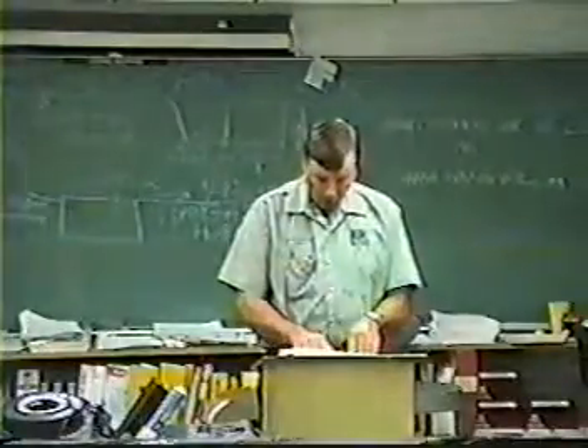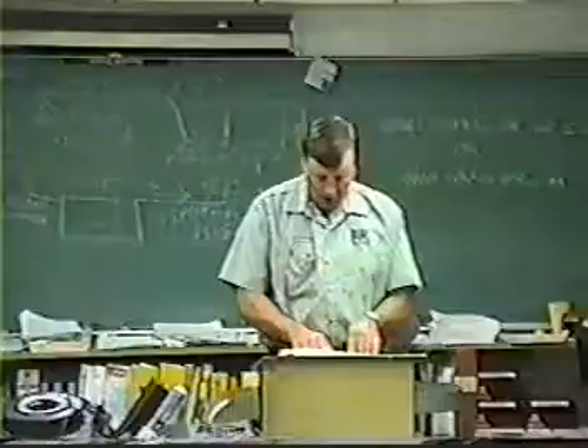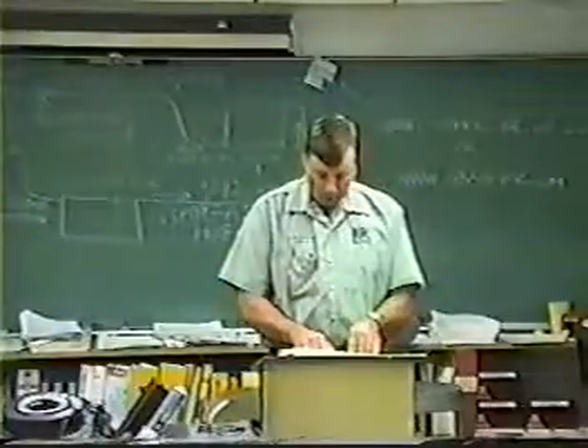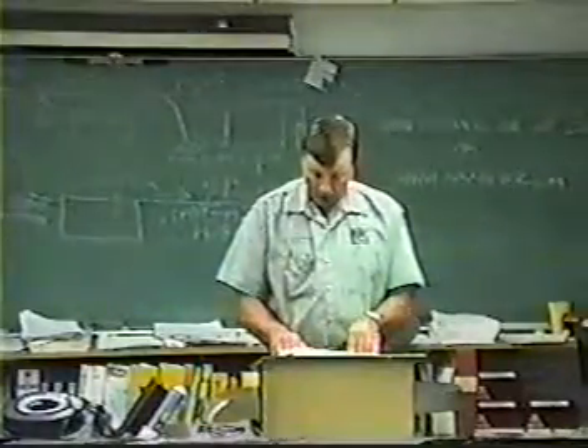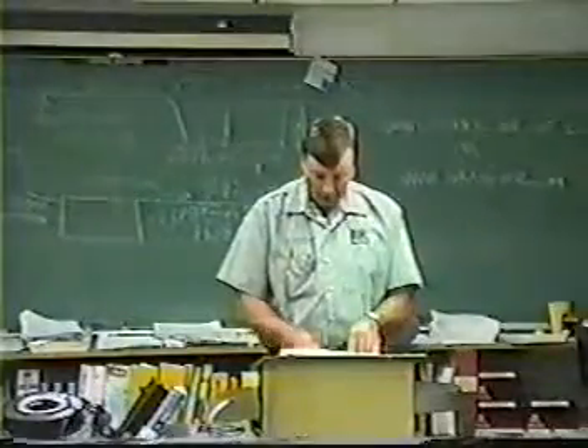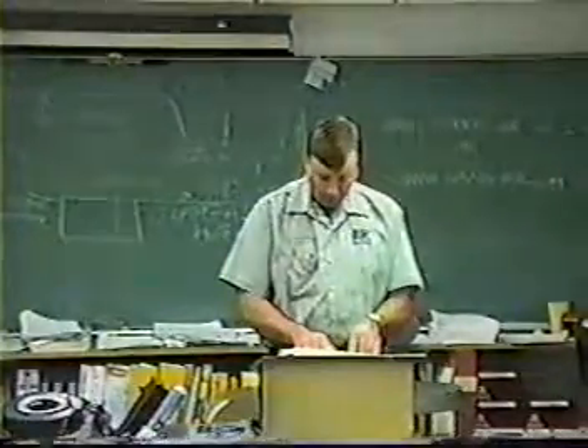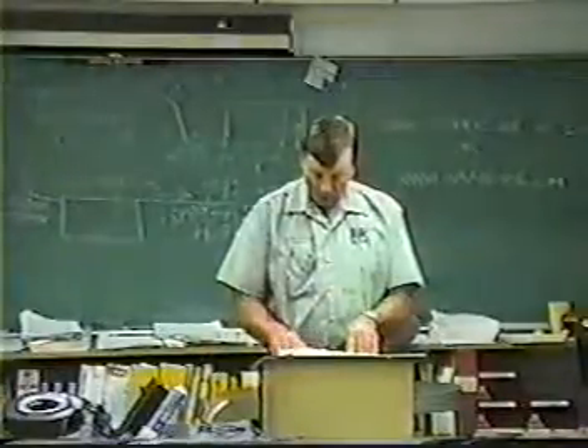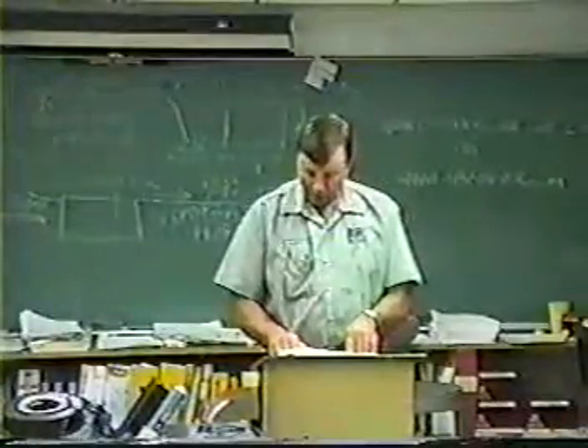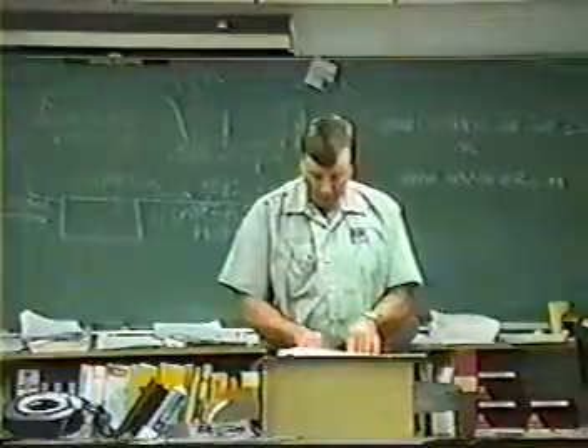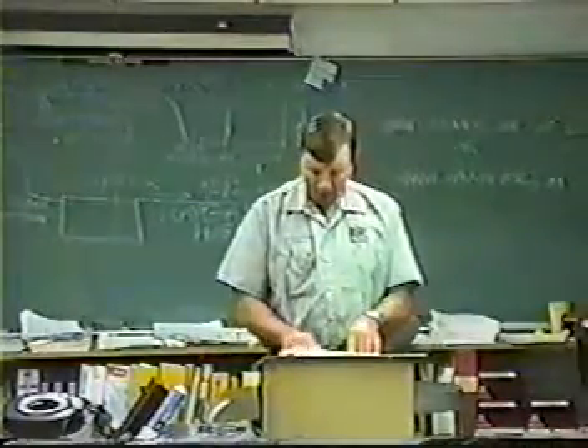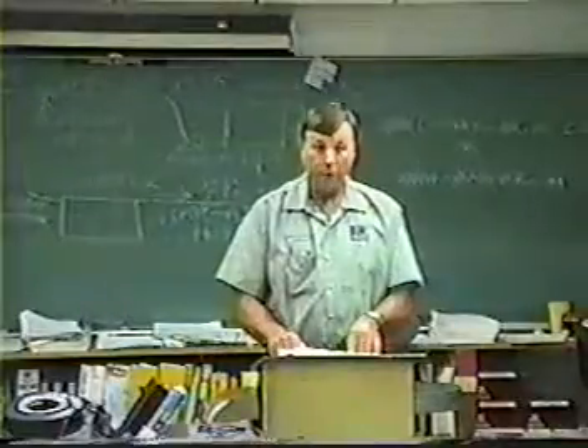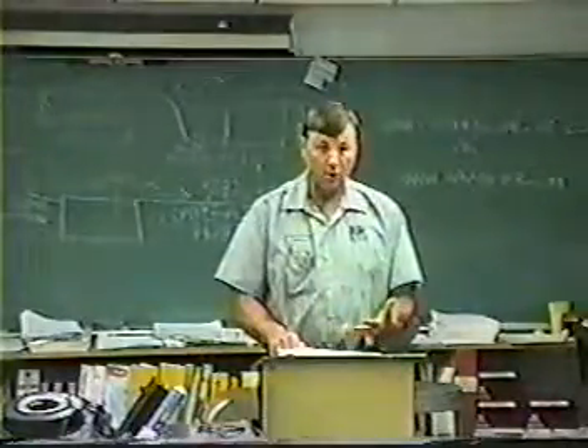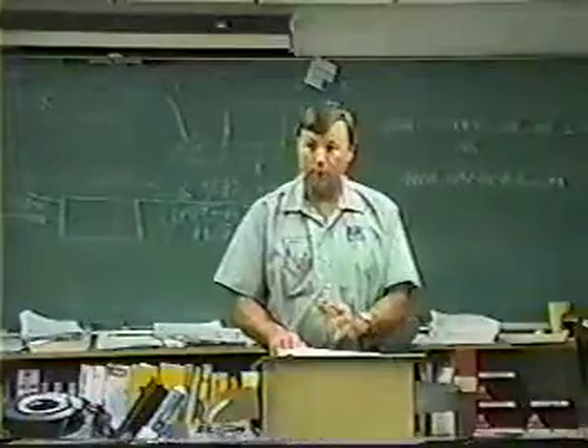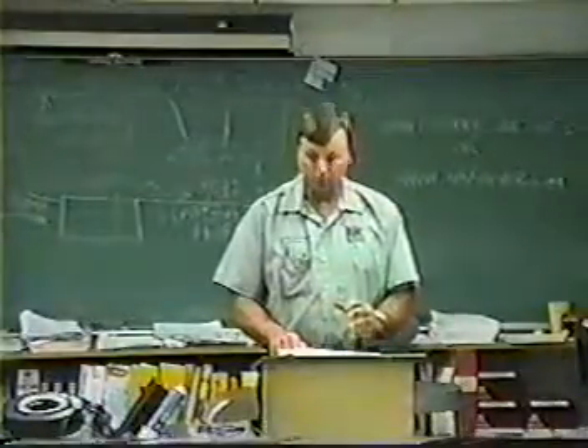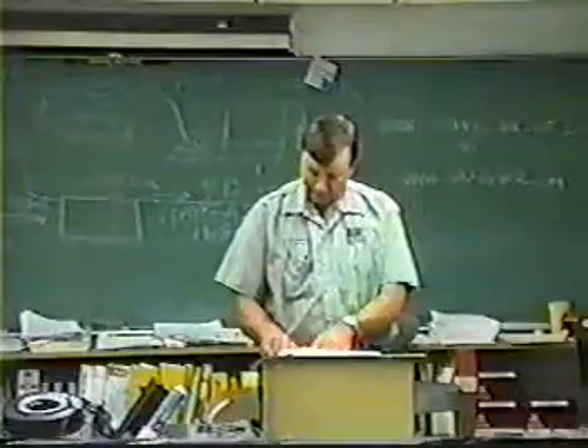If you go to R12 at 4 degrees, look at 37. So you see there's a real close difference in R134A and R12. 37 would be the suction pressure at 4 degrees on R12, and 34.5 would be the suction pressure on 134A. So you see you're right there about 2.5 PSIG difference. So that's why R134A is the universal replacement for Freon 12, because it's so close in pressure. That's how you read that PT chart.